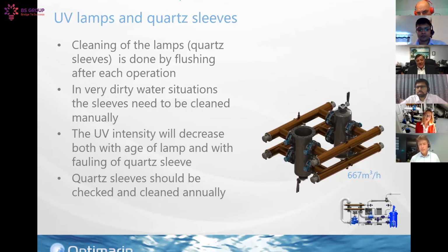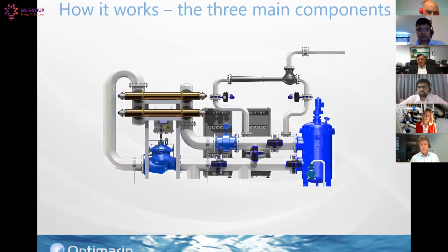If you only run the system in really, really muddy waters, then you need to occasionally take out the quartz sleeves and wipe them clean and then put them back. And the UV intensity meter that is mounted will tell you when the sleeves are getting dirty. And you need to check them once a year anyway.